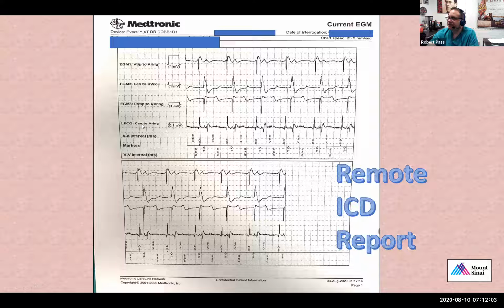And then they're giving us even another electrogram between the device and the ring of the atrial lead. All of these are useful because as you go from download to download to download, it's sometimes useful to compare the electrograms. This is another way for us to confirm that the lead is stable, because it should look relatively similar every time you do this type of test.